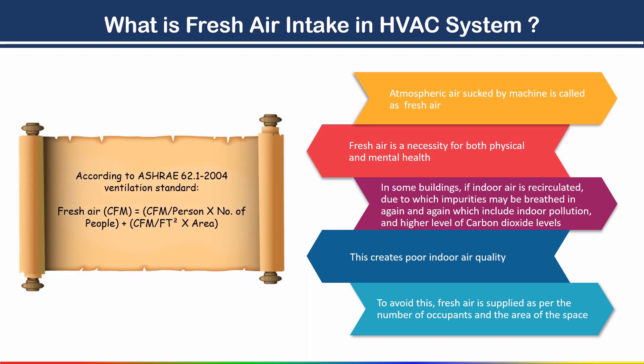According to ASHRAE 62.1-2004 ventilation standard, to find out the fresh air CFM, we use the formula: Fresh Air CFM = (CFM per person × number of people) + (CFM per square feet × area). Using this formula we calculate the fresh air.